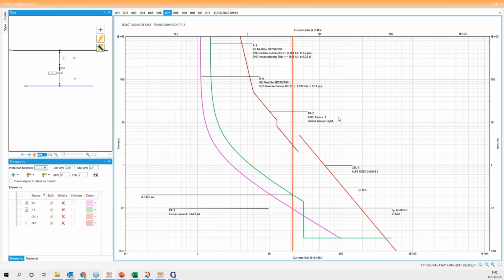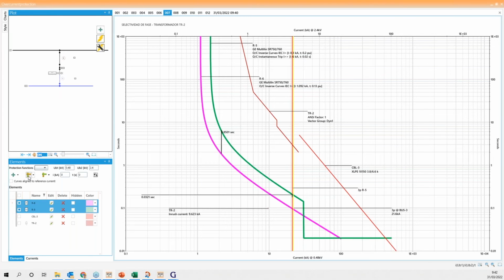For example, if we select this protection and this protection, NEPLAN allows to provide the difference maybe in time between both protections, or maybe in current between both protections. So this selectivity diagram is highly used for the coordination of the protections graphically. And for sure, we can see that the user interface is very user friendly in order to provide the proper selectivities in different parts of the system.